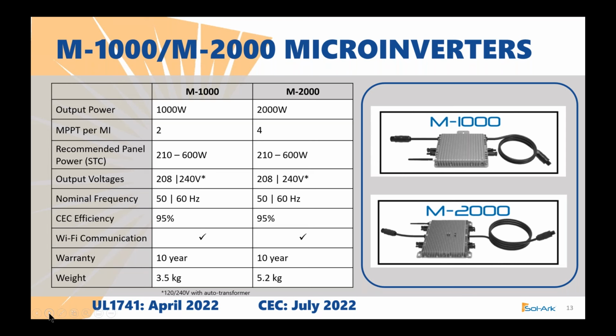You can connect panels up to 600 watts to these—pretty sure that makes these the most powerful microinverters in the world. As far as output voltages, you can see 208 and 240, with an asterisk, and down at the bottom you can get 120/240 volt with an auto transformer. It can do both grid frequencies, 50 and 60 hertz, and has a 95% CEC round trip efficiency.